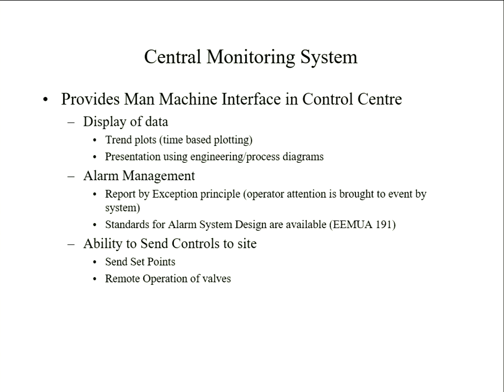But clever alarm handling systems really don't seem to have made their way much. But there is an extent to it. Most of these central monitoring systems, SCADA systems, do allow you to structure alarms into groups. So you might be interested, well, I want to know, maybe, here's all my compressor alarms, here's all this alarm, here's all that alarm, or these ones are critical alarms, these ones are information only. I might have to acknowledge this alarm in a different way to that alarm.